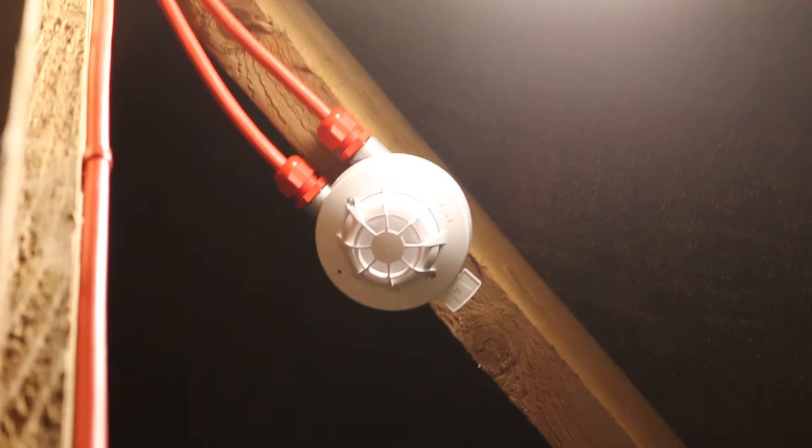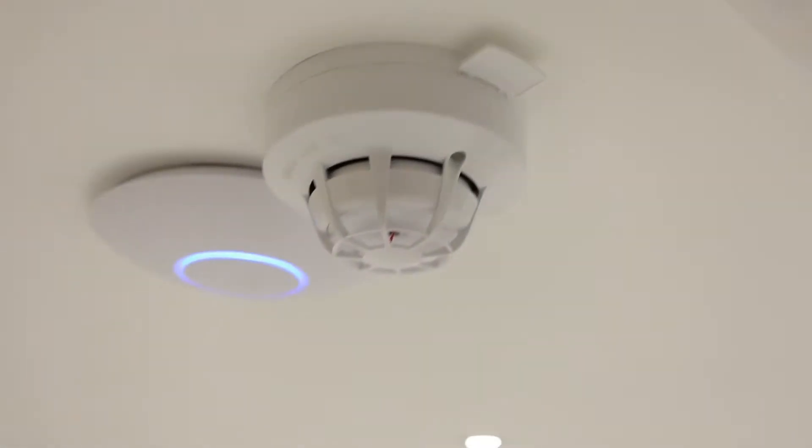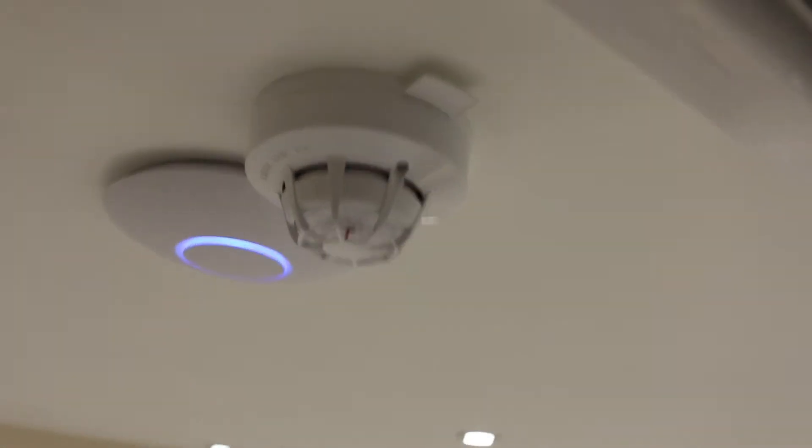The whole system is wired in FP — four core FP 1.5 millimeter solid conductor. The first device is an XP95 multi-sensor; you can see the FP coming in there and it goes down to a Discovery multi-sensor for the actual garage floor. Then we have this call point — a KAC new style XP95 call point which is flush mounted.